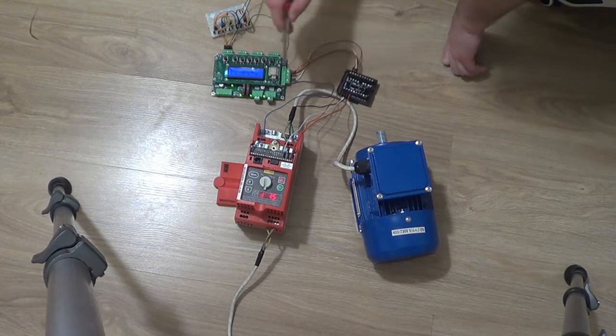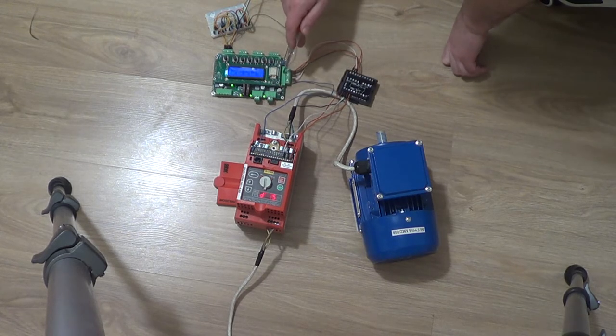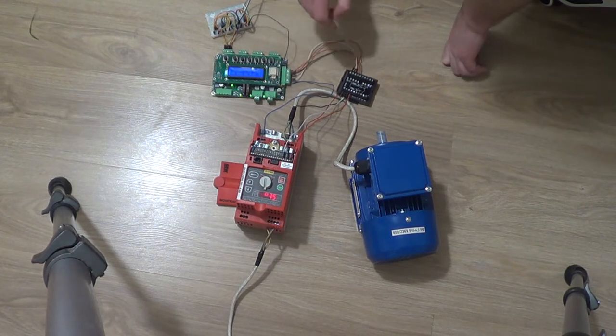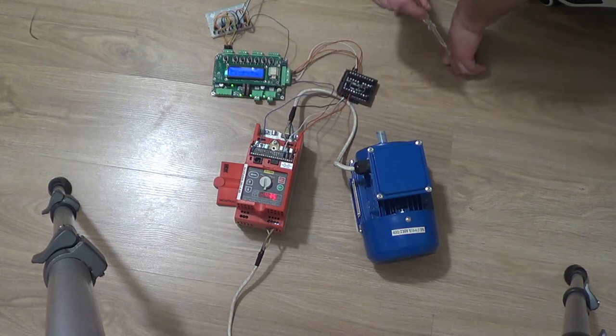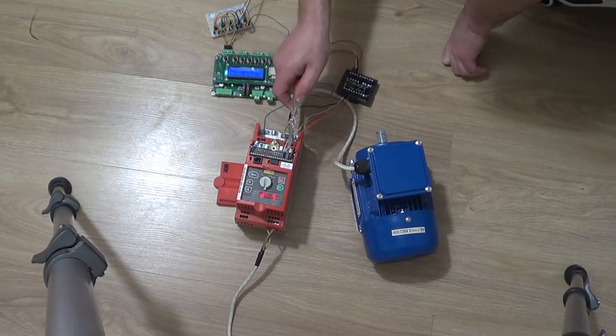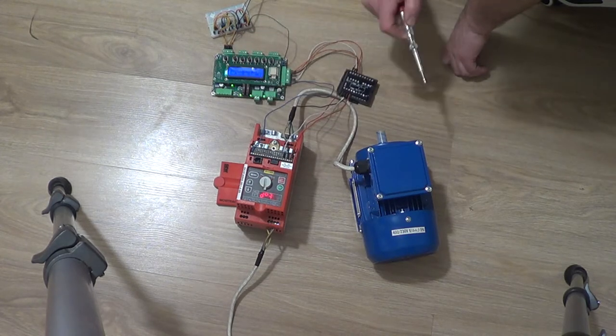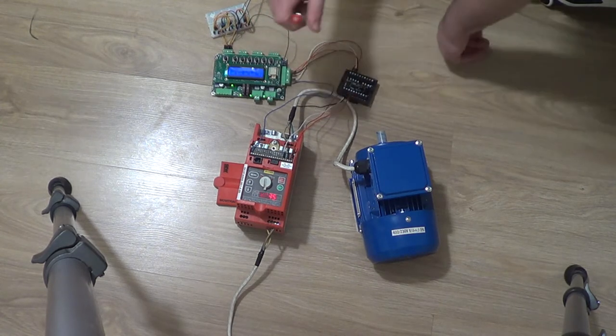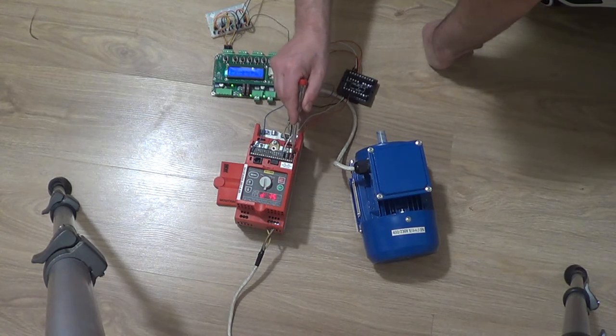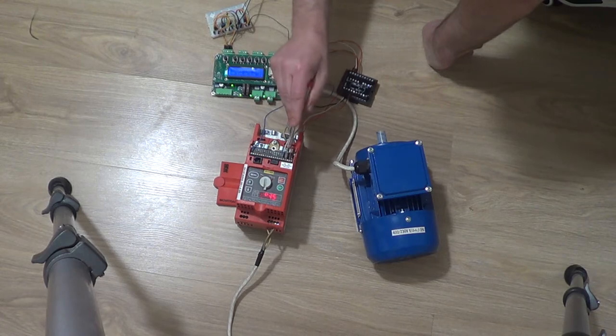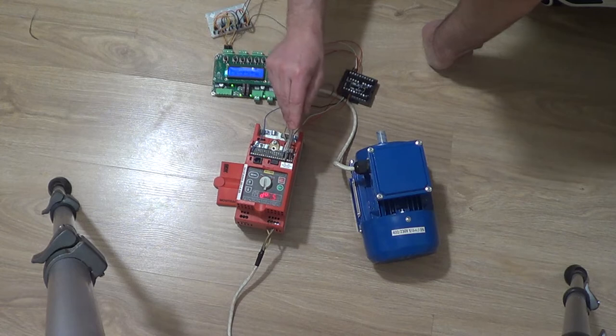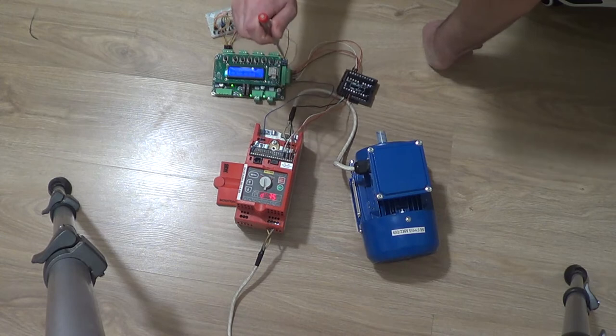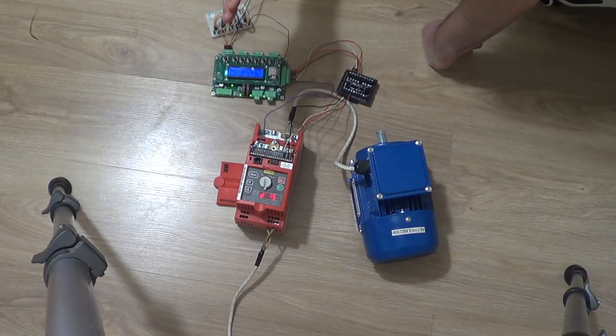This port is important in such case because I'm using here Darlington array. So I'm just sending the grounding signal. And this SEW inverter wants to work in a plus mode. So I have to provide here the voltage to those pins to make sure that inverter will start left, right. Depending on what kind of speed I want to use. And what you see here, this is 24V, this is go left, this is go right. And these are three pins when you can just provide, configure the inverter three different speeds.